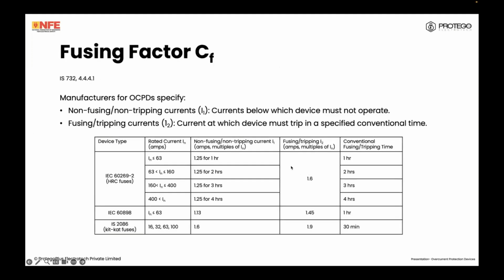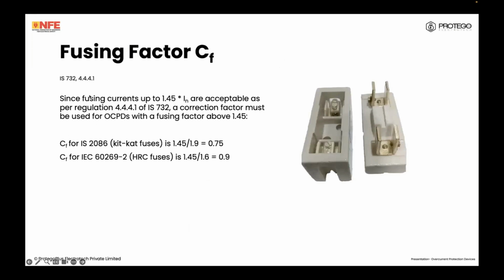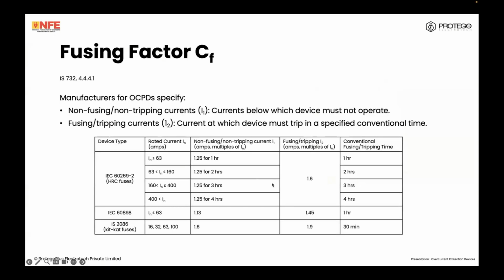And of course, we've got the fusing factor. Now, since fusing currents up to 1.45 times IN are acceptable as per regulation 4.4.4.1 of IS 732, a correction factor must be used for overcurrent protection devices with a fusing factor above 1.45. Now, HRC fuses are very common. They have a fusing factor of 1.6. So 1.45 divided by 1.6 is 0.9.